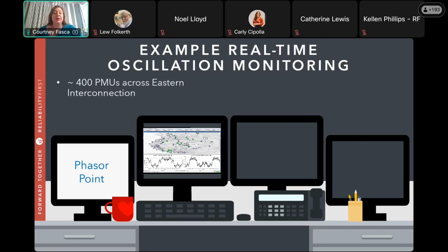So with the online modal decomposition in phasor point, the system dynamics can be decomposed in real time. So basically using that oscillation magnitude and decay time as two metrics to measure the severity of the oscillation. Basically, the bigger the magnitude and the longer the decay time, the more severe the oscillation would be. The reference document states that while it's preferred to avoid alarms on the small, quickly damped oscillations, the lingering ones with the big swings are supposed to be caught by the operators as fast as possible.